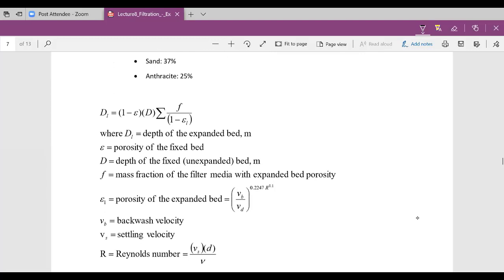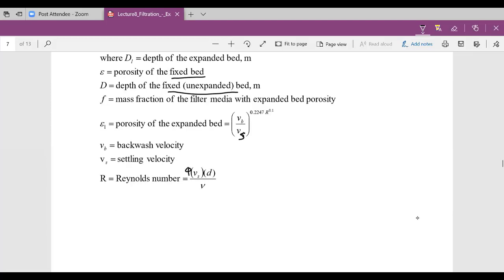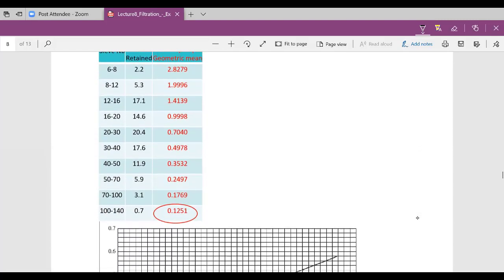The equation we'll use is that the depth of the backwash expanded bed equals 1 minus the porosity of the fixed bed, times the depth of the fixed bed during operation, times the summation of the filter media with expanded bed porosity. The porosity of the expanded bed is a function of the backwash velocity and the terminal settling velocity of each particle grain size. We'll include the shape factor in the Reynolds number.